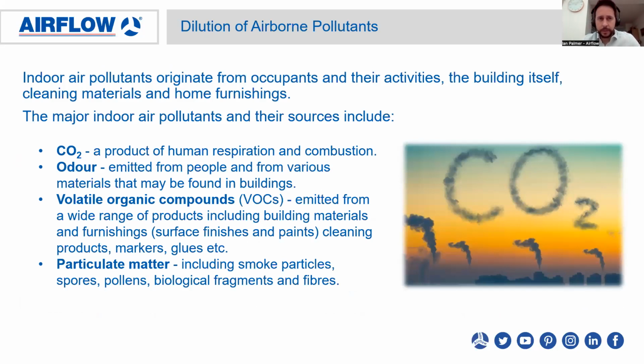So with the dilution of airborne pollutants, there's a number of pollutants that can be found in the home, and some of the most common pollutants are CO2, odor, volatile organic compounds, VOCs, and particulate matter. So it's very important that we extract these pollutants from the space and dilute them by supplying fresh air into the building.